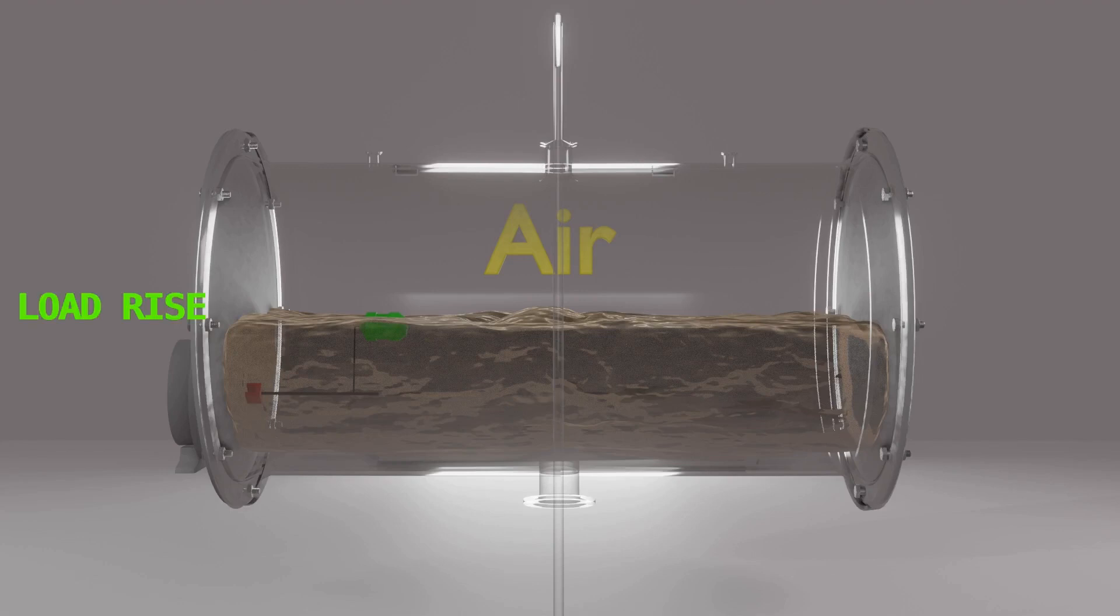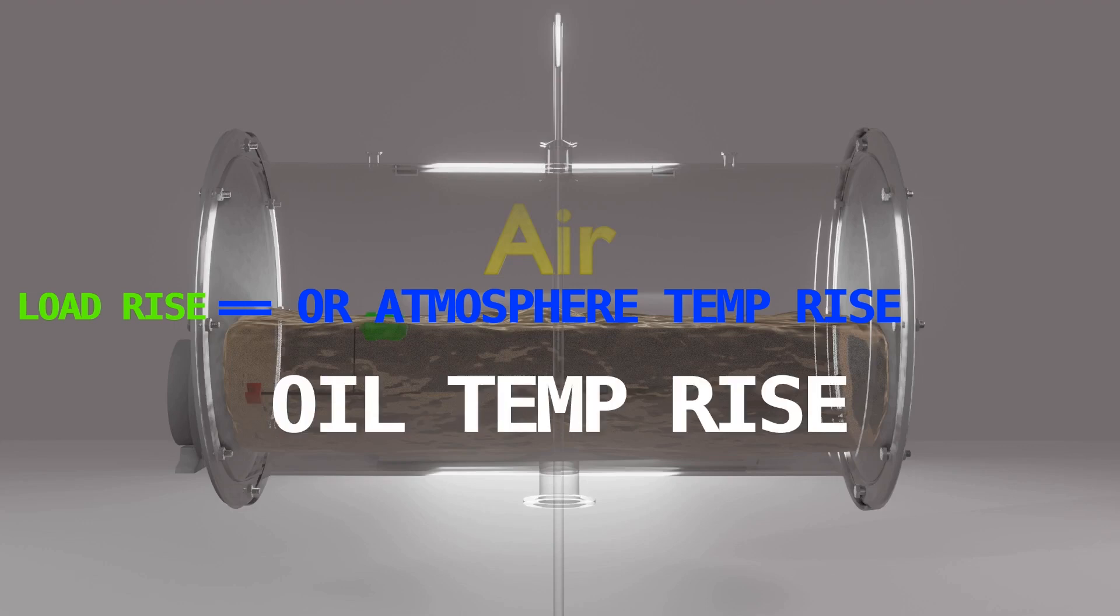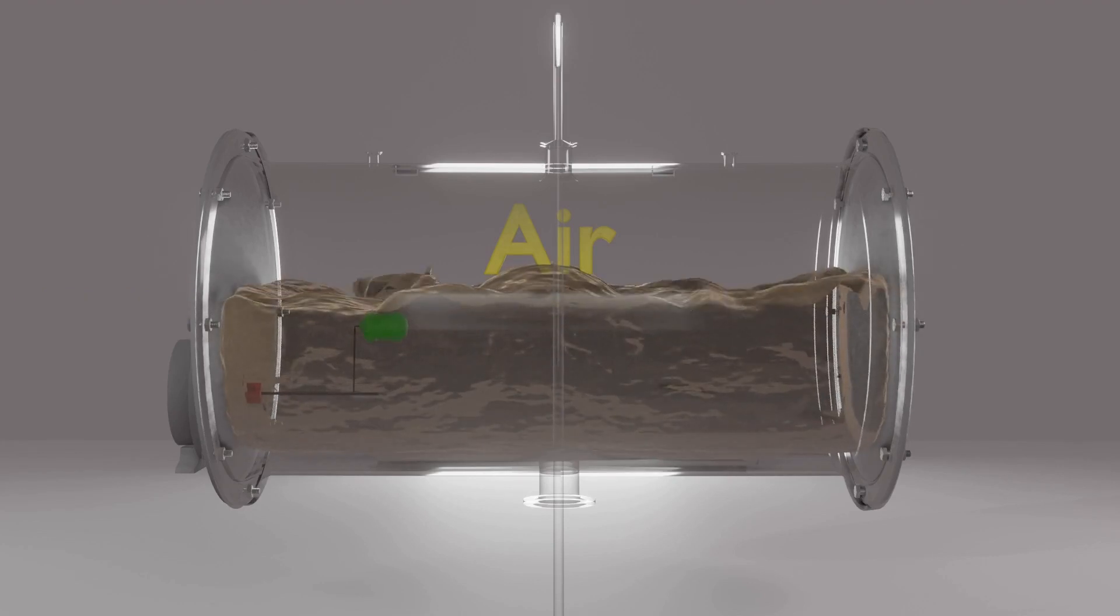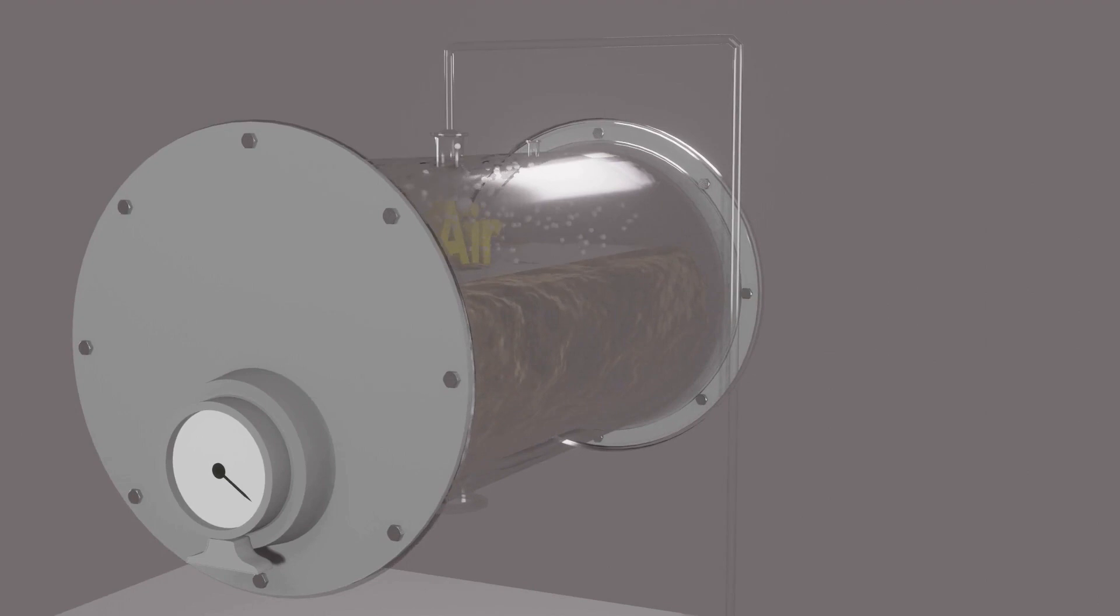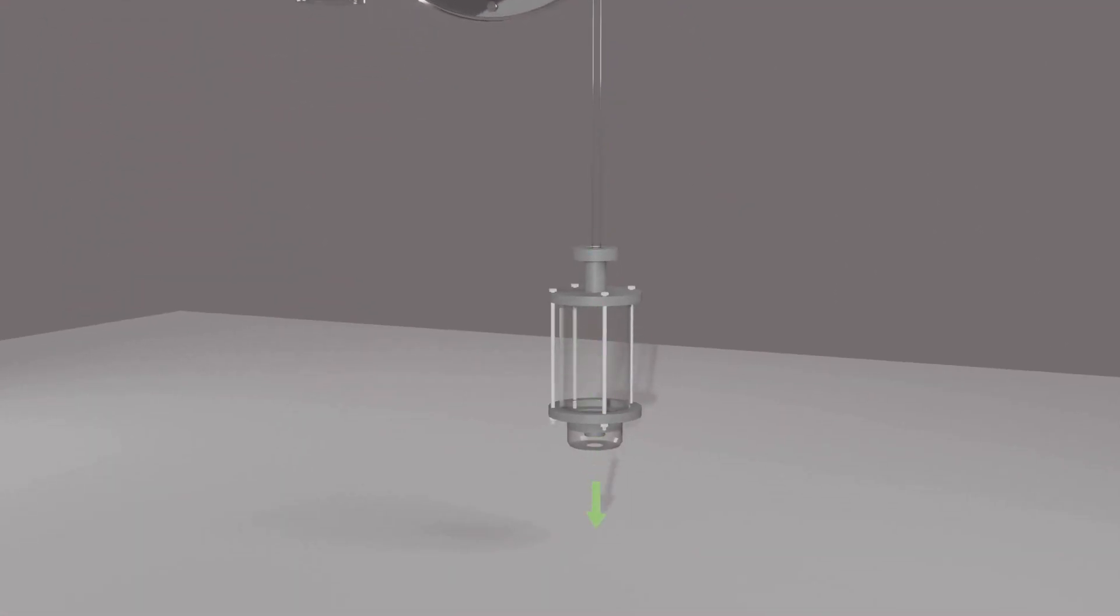Now suppose the load on transformer increases or atmospheric temperature rises, then it will raise the temperature of oil. Due to that, oil expands over the empty space as much as required, and the air available at empty space gets out from this breathing pipe through the breather to atmosphere, as you see here.